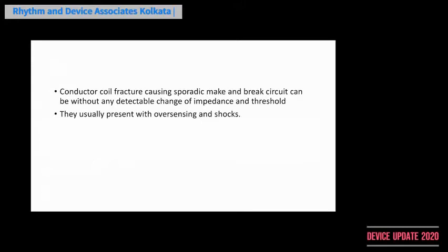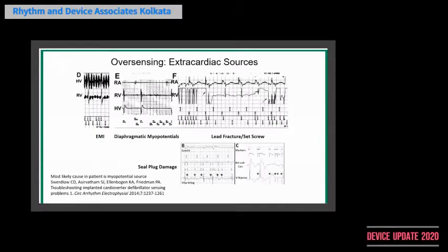And usually they present with oversensing and shocks. So these are the different causes, I have already discussed all these things: myopotentials, EMI, lead fracture, and seal plug damage. I'm not going to detail.